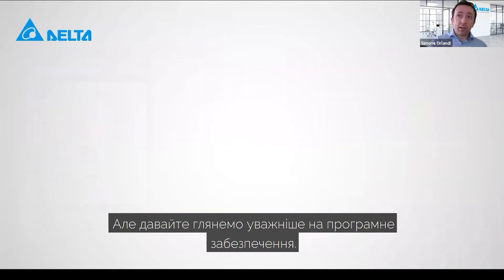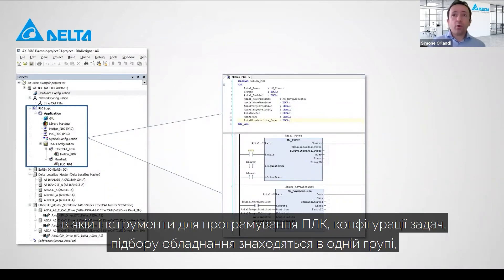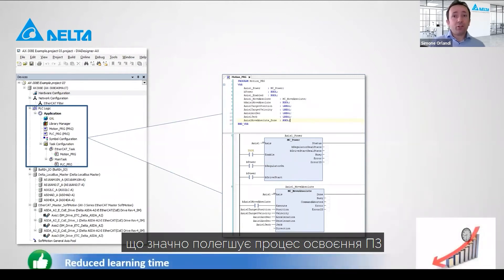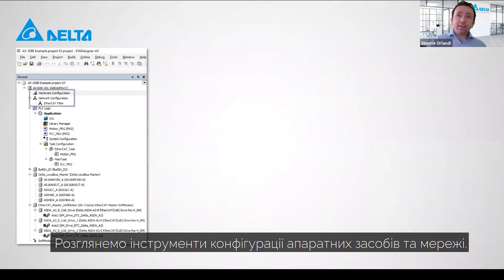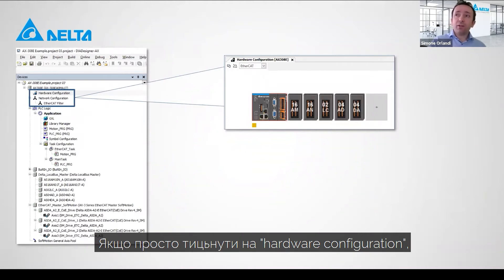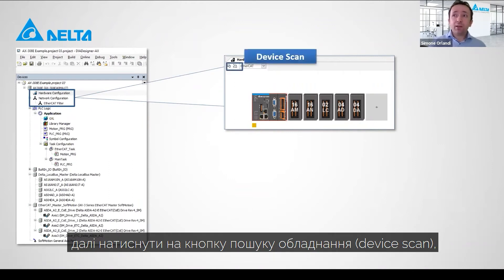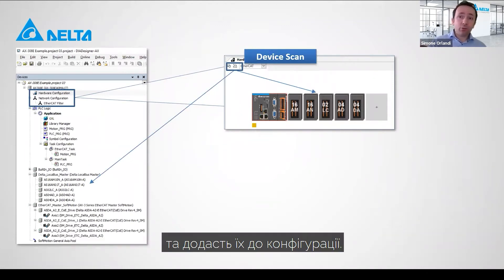Let's have a look at the software now. DIA Designer AX keeps the typical project tree structure, where PLC programming, task configuration, and hardware configuration are all available in the same environment. This will dramatically reduce learning time and make you able to develop a complete project from day one. Delta added tools on top of Codesys, for example, the hardware and network configuration tools. By simply clicking on the hardware configuration and clicking the device scan button, the system will automatically detect connected IO modules and add them into the configuration.